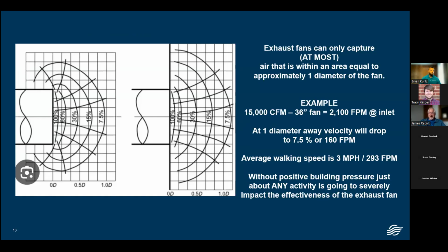Exhaust fans can only capture, at most, air within an area equal to about one diameter of the fan. In that graphic on the left is an image of an exhaust duct going into the building, protruding into a space. You can see on that plane 0 diameter, 0.5 diameter, 1 diameter. Look at how quickly the velocity degrades as you get away from it, down to 7.5%. You can be 1 diameter away and hardly feel that air moving.